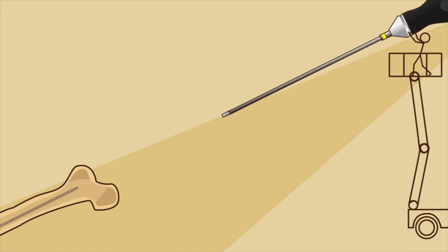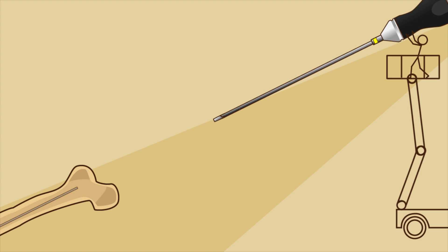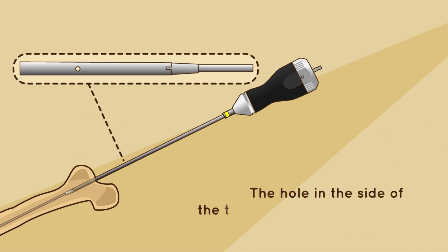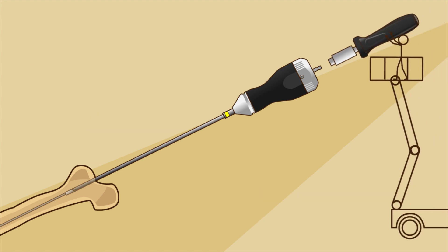Step 2. Under fluoroscopy, locate the end of the male component and mount the male retriever onto it. Make sure that the end of the male component is fully inserted into the male retriever before tightening. The hole in the side of the tube should not be visible. Mount the torque handle.